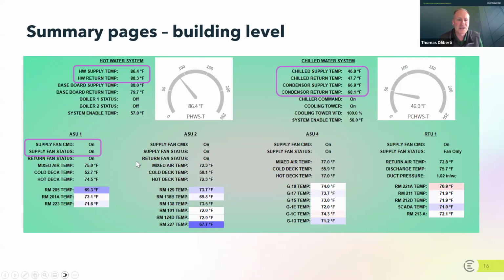Another thing I wanted to use this slide for is this idea of a supply fan command and a supply fan status. These two different descriptors are very common with building automation systems, command points and status points. What this is saying is this supply fan is being commanded on. So the system is saying, fan, you need to run. And this point here, the status point, is telling you what it's actually doing. When these two things differ is when you have a problem. These two things should always be in sync, and it helps you understand better what's happening downstream.